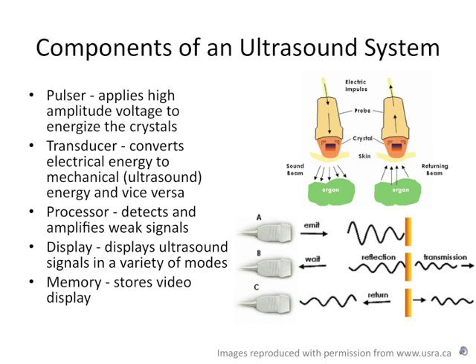On return to the transducer, reflected ultrasound waves are transformed, due to the direct piezoelectric effect, into electrical energy. This electrical energy is received by a processor, which detects and amplifies these weak electrical signals before displaying them as an image. A memory system is also usually incorporated to enable the storage of images.